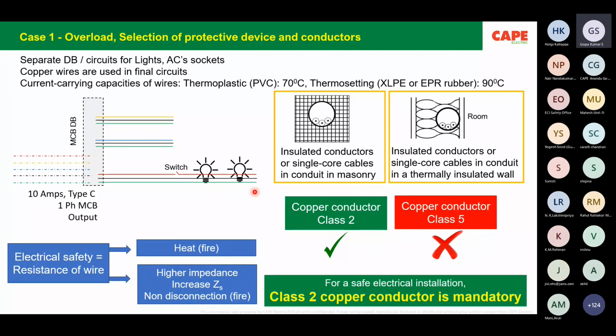So now, when it comes to the selection of wires, it is not the plastic but the copper that we have to be a little bit more careful about. Copper conductors, flexible wires: there are two types available, copper conductor class 2 and copper conductor class 5. Class 5 copper conductor has about 8 to 9% higher resistance in comparison to class 2 copper. That means class 5 is cheaper, because class 2 has a little bit more copper, maybe pure copper. As a result, it is a little bit expensive.